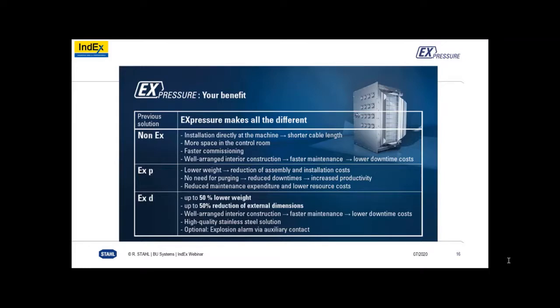You have a more compact installation and more functionality, and you must open or close only one enclosure. You have shorter downtime, less loss of production, and a better overview, for example, during maintenance. It reduces the time for the failure search because you don't have to open a combination of several Ex enclosures and search for the failures. You have to open only one.